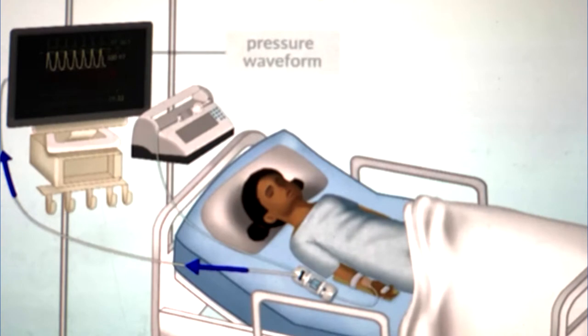This is a diagram of the setup. Basically you've got your art line connected to your patient via some semi-rigid tubing. This is the pressure transducer, which has a connection to either a fluid bag or a syringe with saline in it, and also a graphical display of the pulse waveform, whether it be a SurgiVet or a Cardell.